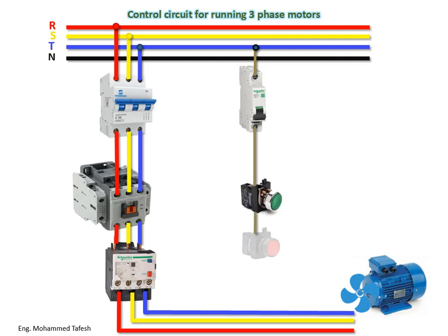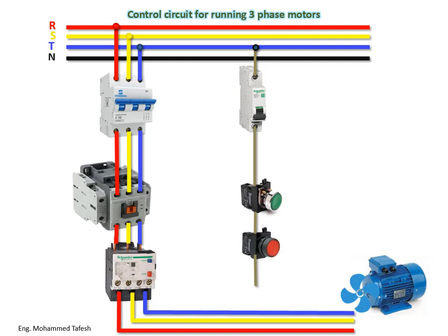After that, we connect to the stop switch — the push button OFF. It works in reverse: it disconnects the electric current from the circuit when pressed. The connection continues to contact points 95 and 96 on the overload, and then to the entrance of the contactor coil A1 and A2, which is responsible for magnetizing the contactor. This works to connect the power poles of the contactor and connect the auxiliary contacts while opening other contacts.